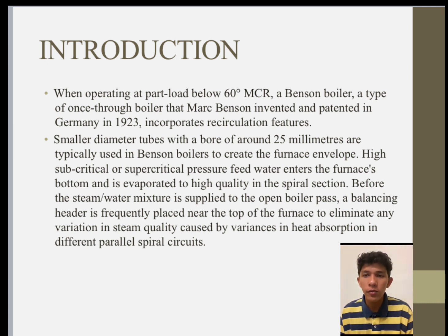Before the steam-water mixture is supplied to the open boiler pass, a balancing header is frequently placed near the top of the furnace to eliminate any variation in steam quality caused by variations in heat absorption in different parallel spiral circuits.